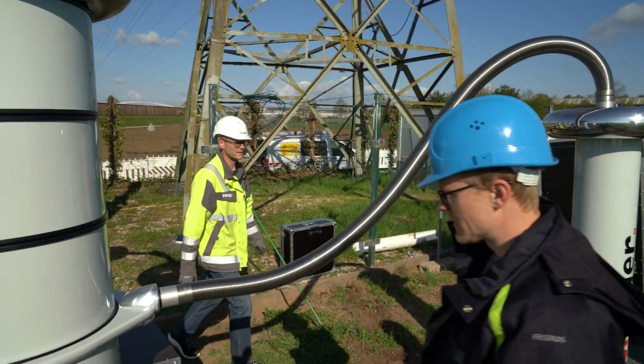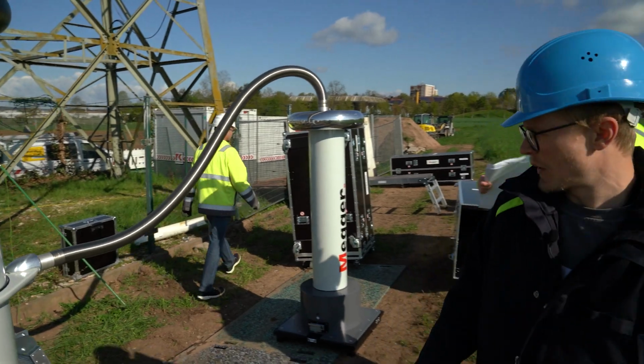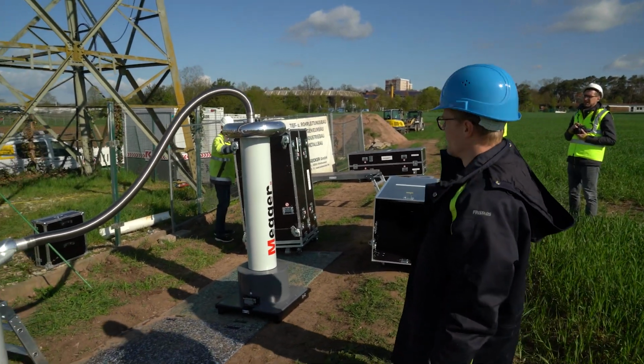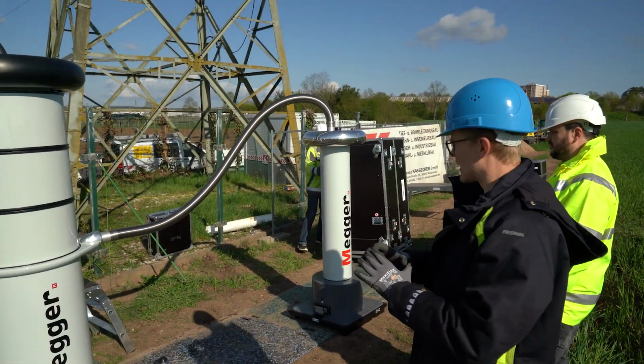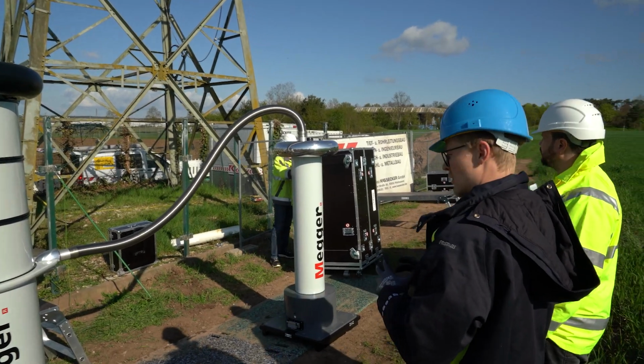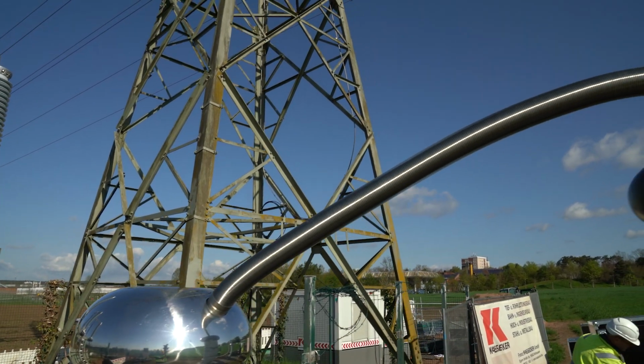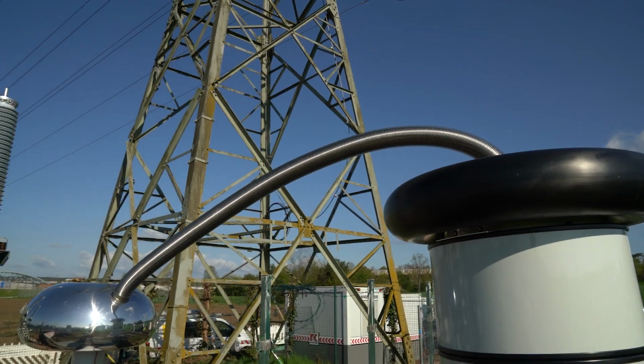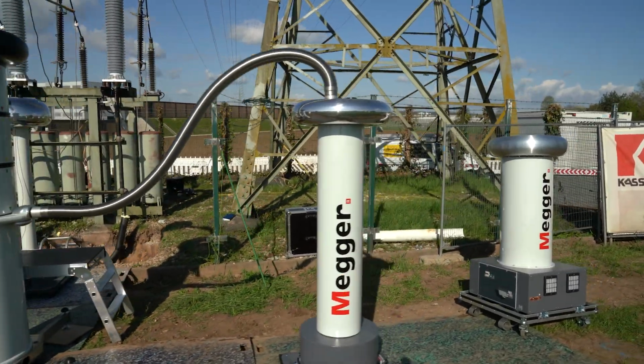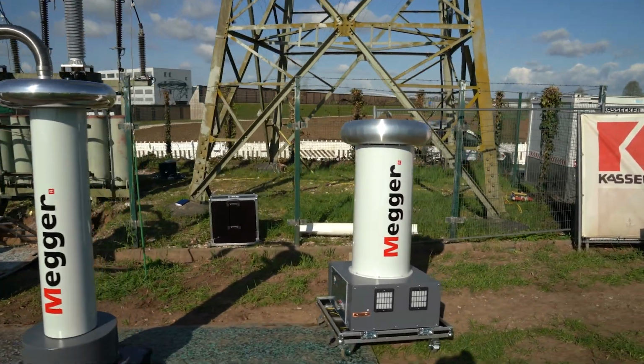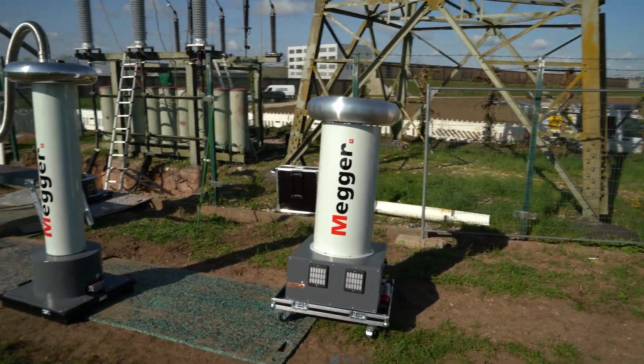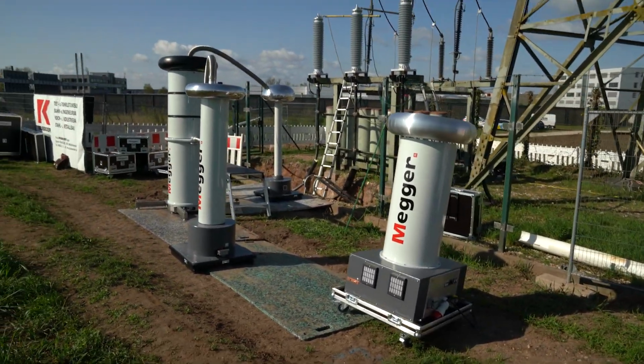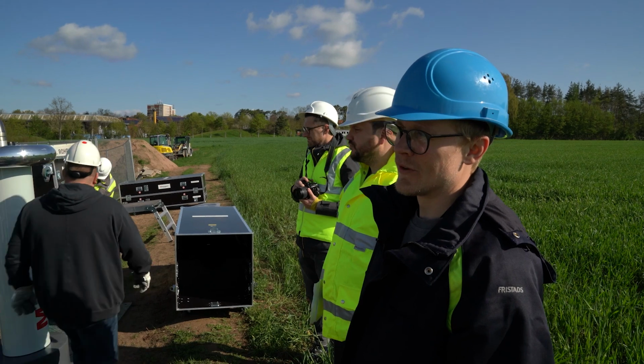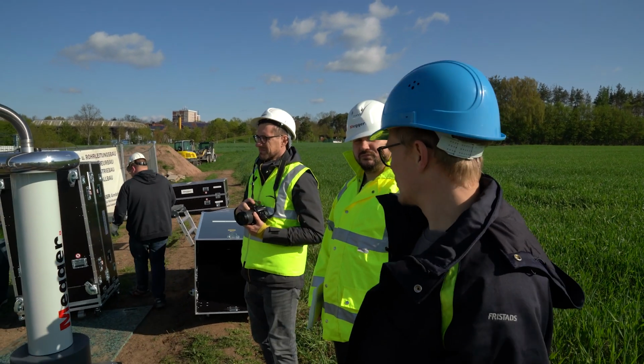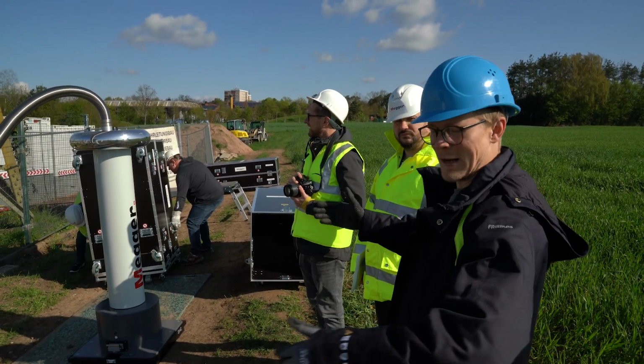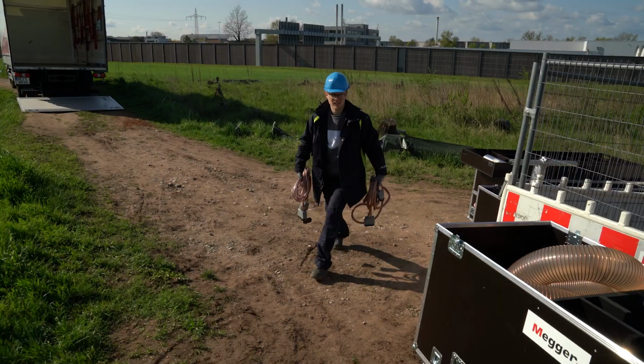This is known as a high-voltage connection. We must maintain the largest possible radii. Otherwise, there may be problems with corona discharges in the event of high voltages. That is why these connections are always very large. Their purpose is not to transmit as much power as possible, but simply to have large radii. We want to measure the discharges in the cable, and we need to do everything we can to prevent other discharges, for example, due to small radii.